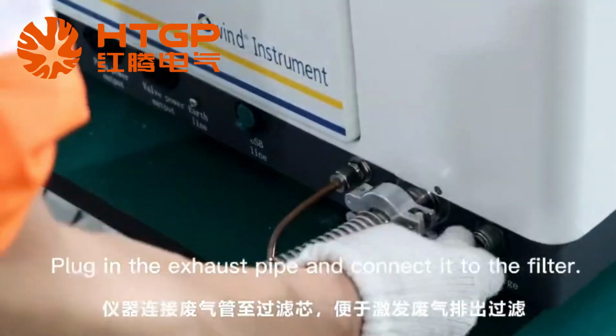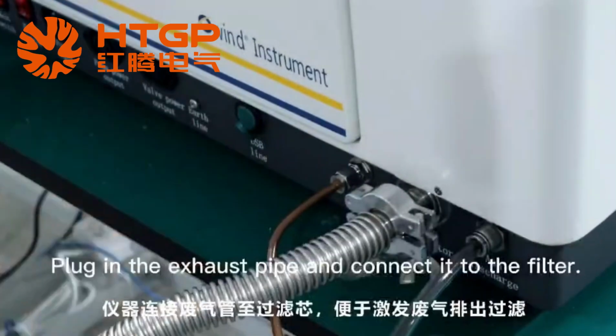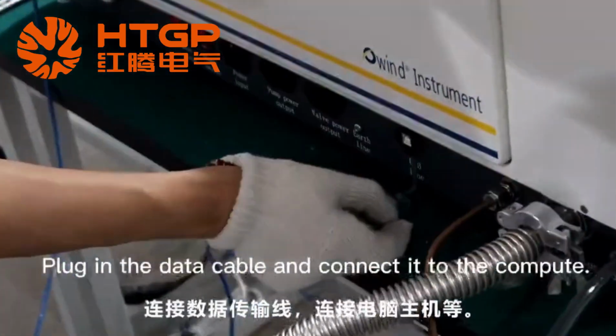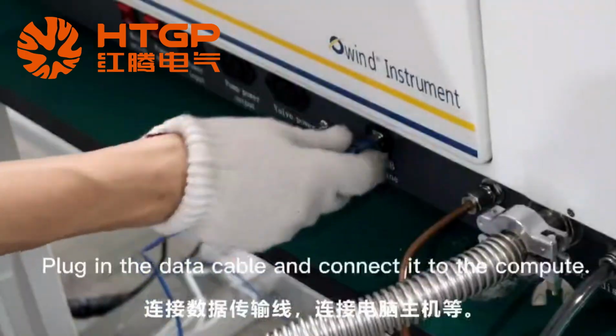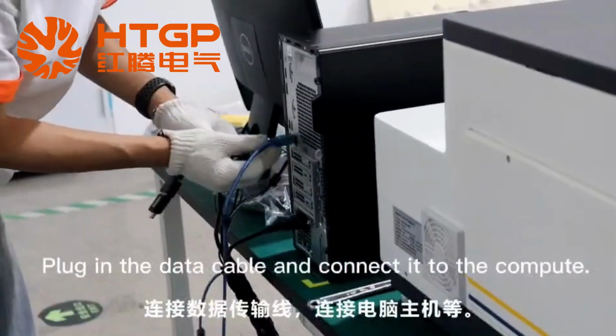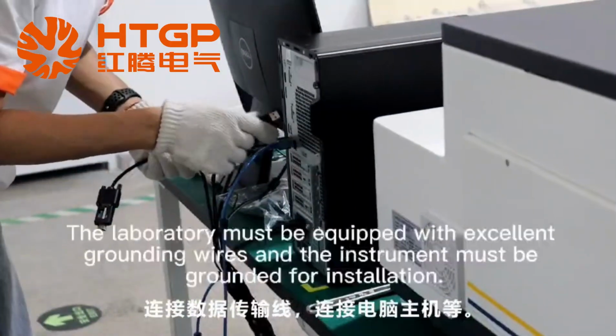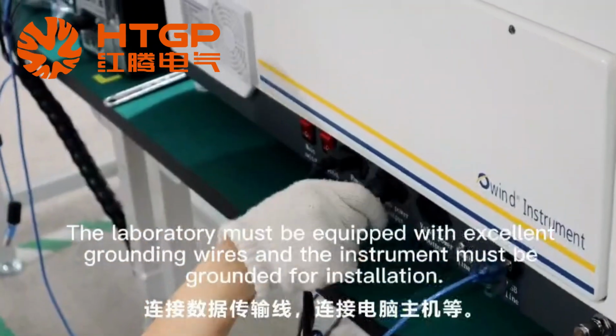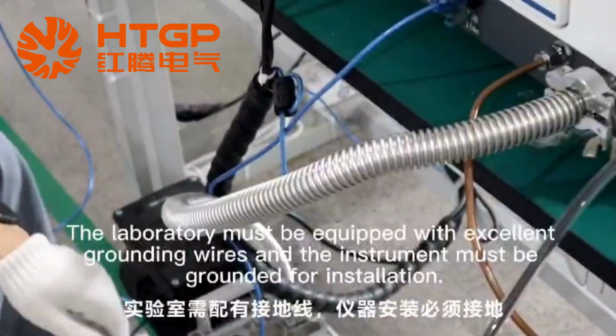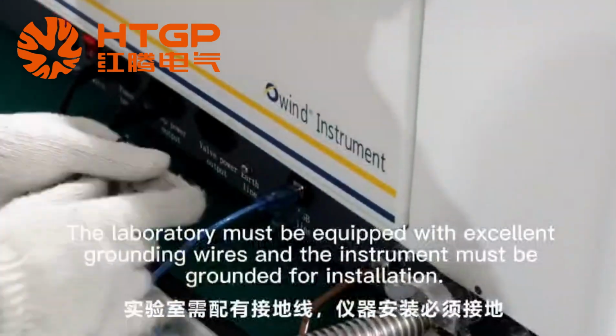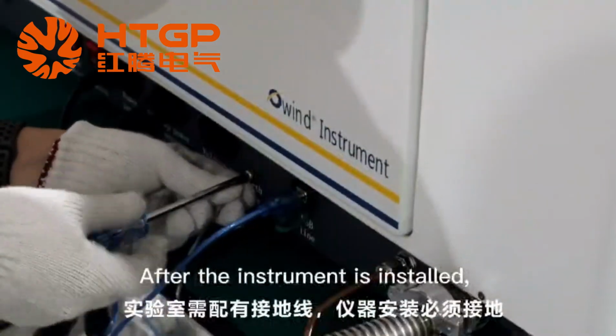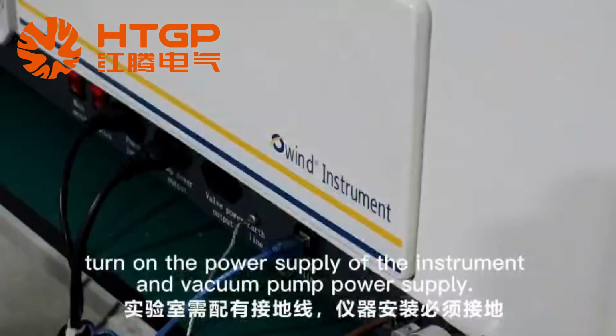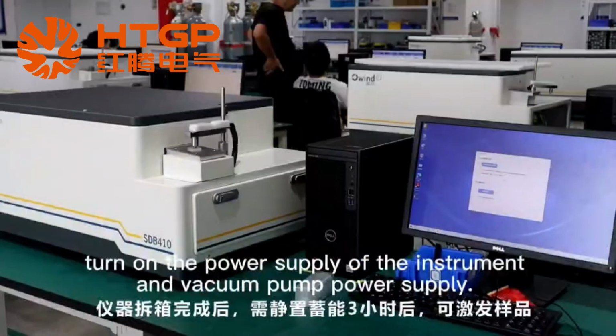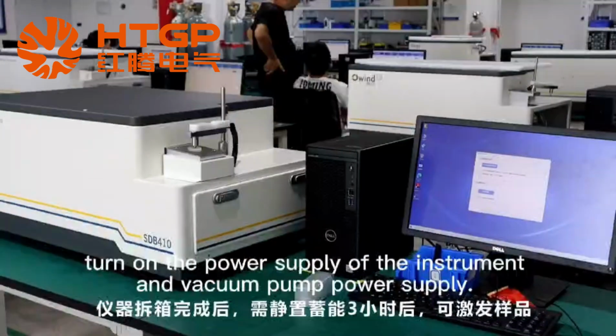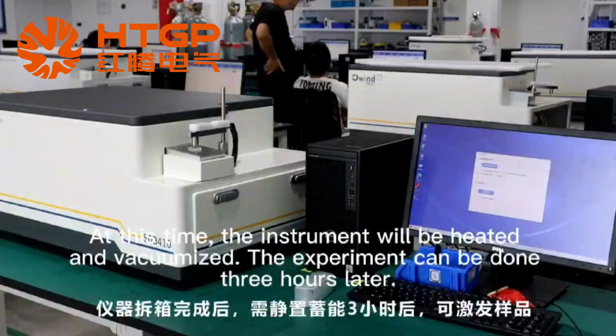Plug in the exhaust pipe and connect it to the filter. Plug in the data cable and connect it to the computer. The laboratory must be equipped with excellent grounding wires and the instrument must be grounded for installation. After the instrument is installed, turn on the power supply of the instrument and the vacuum pump power supply. At this time, the instrument will be heated and vacuumized. The experiment can be done 3 hours later.